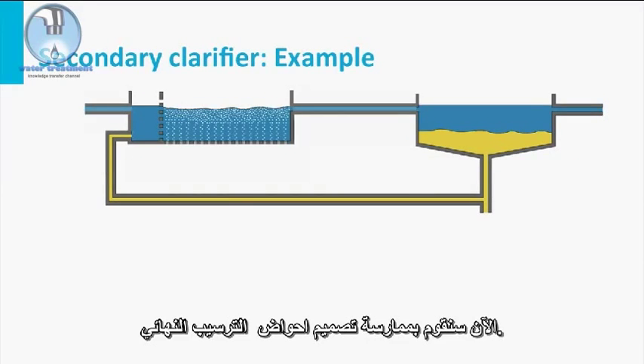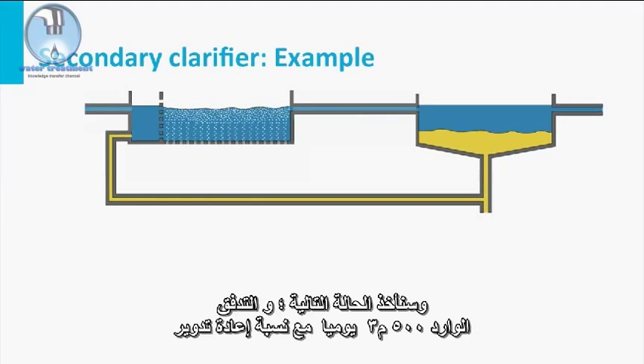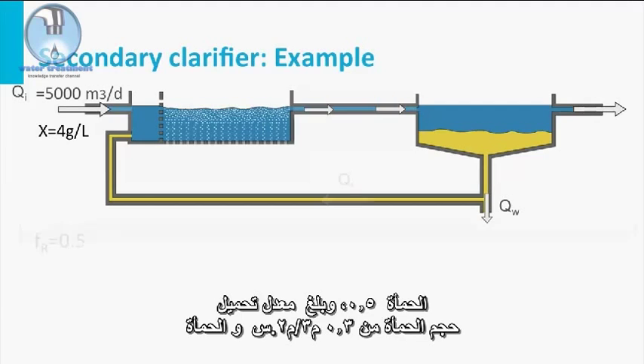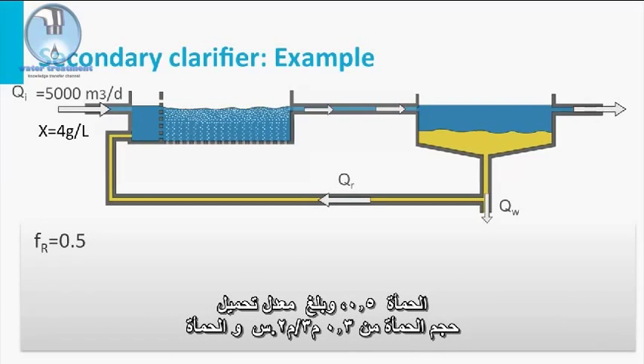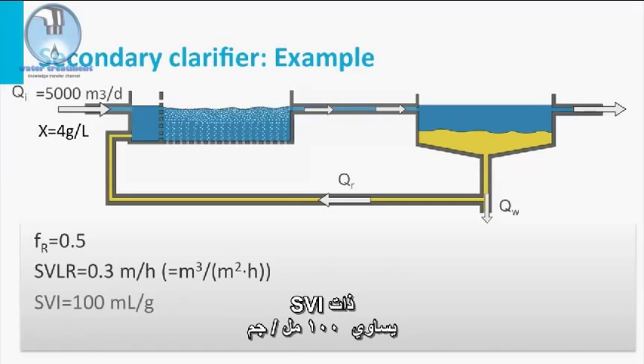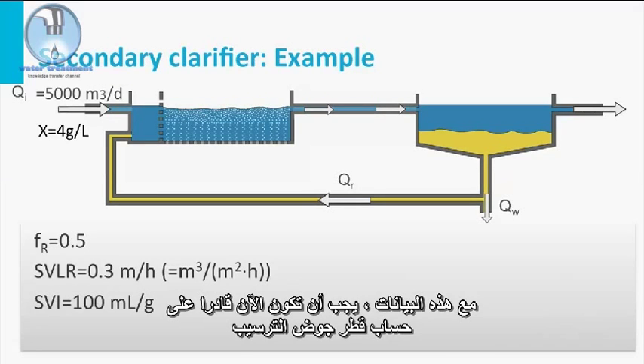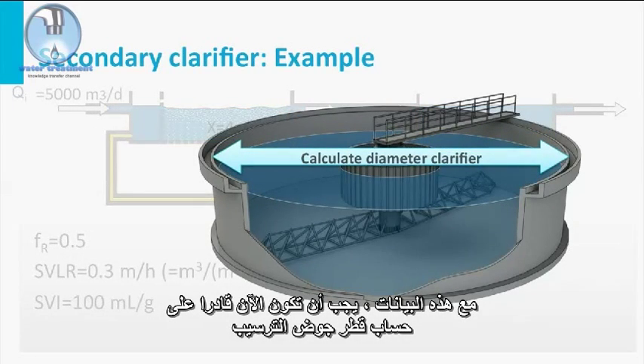Now we will practice designing a final clarifier. We take the following situation: an influent flow of 5,000 cubic meters per day combined with a sludge recycling ratio of 0.5, a given sludge volume loading rate of 0.3 cubic meters per square meter per hour, and the sludge has an SVI (sludge volume index) of 100 milliliters per gram. With these data, you should now be able to calculate the diameter of the settling tank.